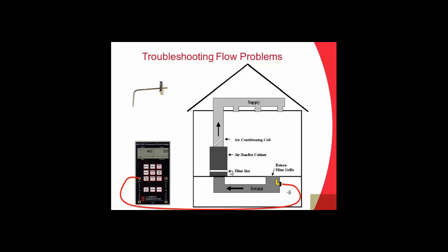And in this case, it's not a filter grill. We're putting a filter slot over here to take that measurement at that location. So we're measuring the pressure across that return grill to see how restrictive that return grill is. And then now we're taking a measurement just before the filter in the return duct, and we're seeing a -28 at that location. So that -28 is the pressure difference between these two locations. So we've got a pressure drop, right? We have to think of this as a pressure drop. We're getting more negative. The pressure's going down. And whenever we get a pressure drop, that's because we've got some restrictions in the airflow. And in this case, a couple of elbows and a long length of duct are causing that drop in pressure.